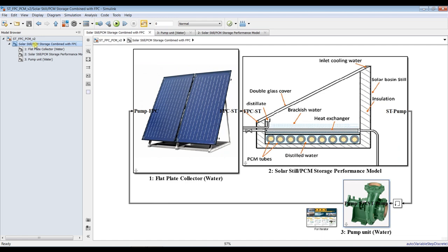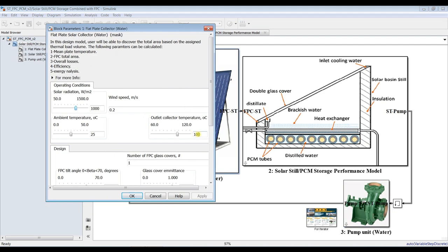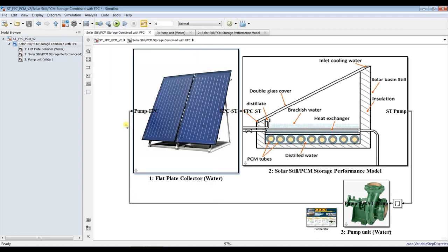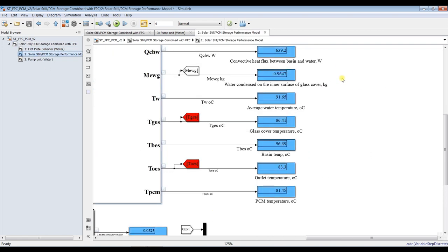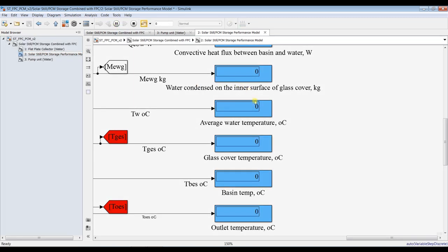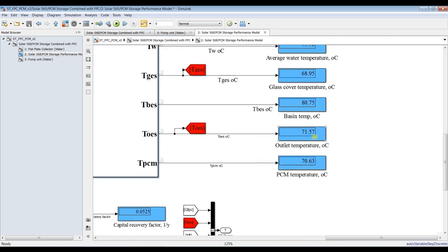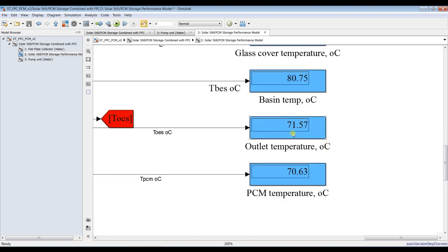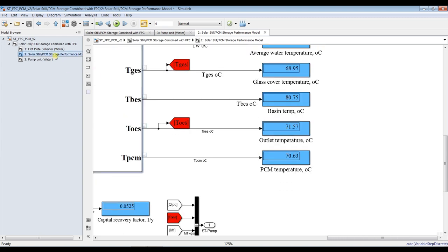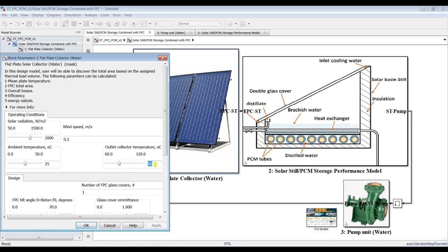Suppose I need to specify different operating conditions — let's go for 80 degrees Celsius as the top cycle temperature, so output going to the solar still is 80 degrees Celsius. We have to realize the effect on productivity: decreasing the temperature should decrease productivity — that's quite normal — and should also decrease the output temperature going back to the flat plate solar collector. From 80 degrees, the stream will lose some heat through heat transfer losses, and the temperature would drop to 71 degrees Celsius. That's quite logical.